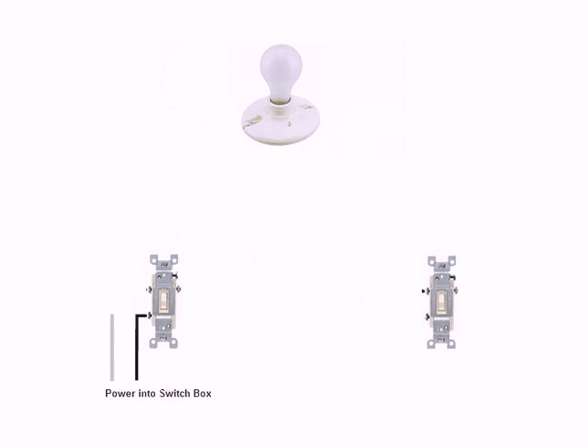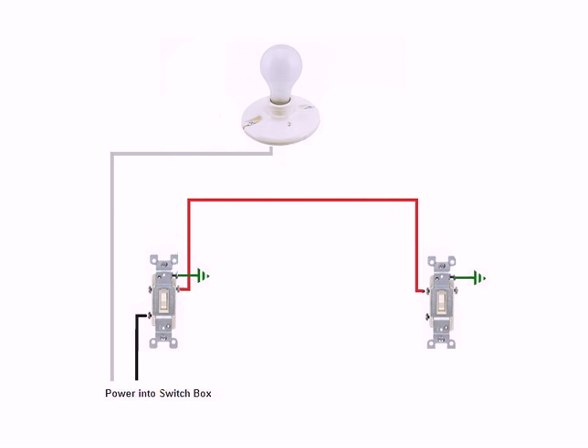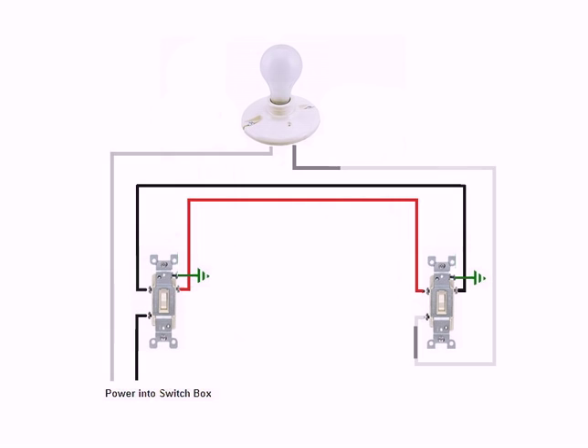Then what we have, a typical switch scenario has power coming in, grounded switches and light fixtures, a neutral wire that goes up to the light fixture, and then what they call travelers that go in between the three-way switches. We've got two different sets of wires for the travelers. Then you've got a switch leg that goes up to the light fixture.